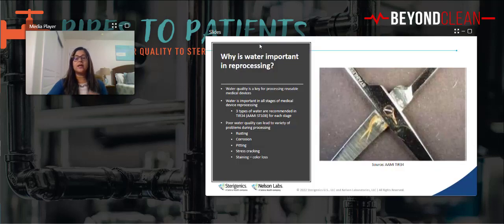Now to start with, why water is important in reprocessing. We all know water is a key quality process, right? Without it, we're not going to get anything cleaned. We have to ensure that the water is of stellar quality when we're preparing detergents and when we're rinsing the devices. We want to make sure that our washers don't have any scaling on them. That's why we want to ensure that mineral deposits are not there and bacterial contamination is lower. So it's very important that for the key metrics you're measuring for water, you have that system in your facility to move on with it.